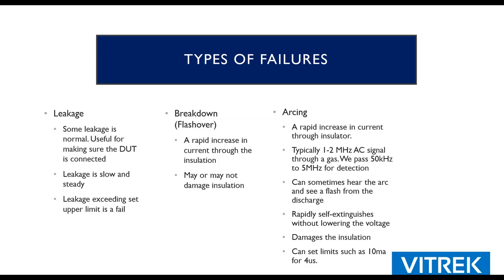You can also have a breakdown, which sometimes is confused with an arc. It kind of just depends on the way you use the word, but sometimes there'll be an audible flashover. You'll hear it break down, and that's a very easy thing to detect. With the V7X, we have breakdown only mode. You're not required to set a leakage current limit. You just say that I do not want my product to break down, and we take care of it from there. And the other thing is arcing.